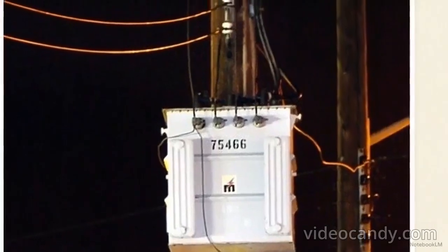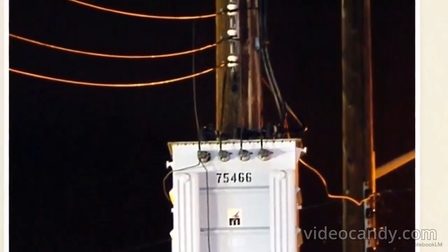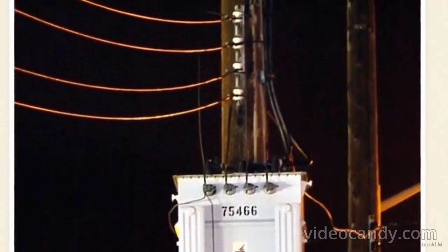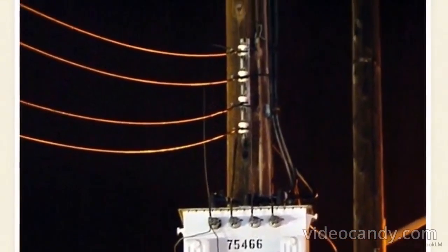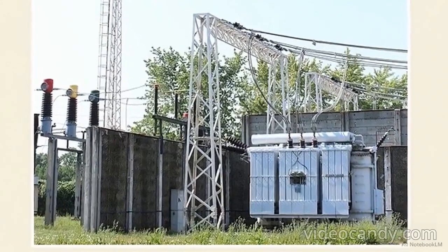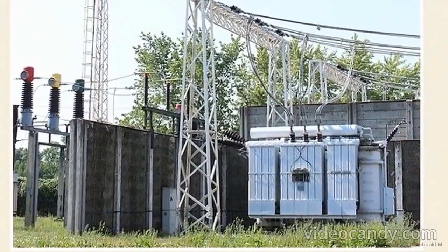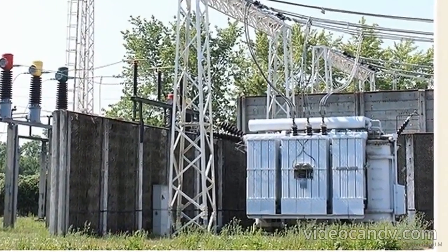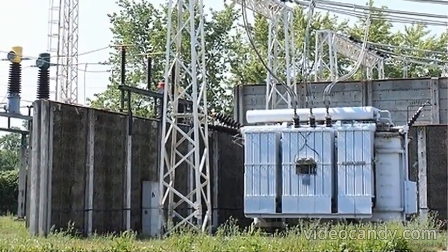Early on, scaling up power meant scaling out. To manage three-phase systems, engineers simply wired three separate single-phase transformers together. Today, that approach is largely replaced. At a modern substation, you'll see a single, massive core-type transformer handling the entire three-phase load.